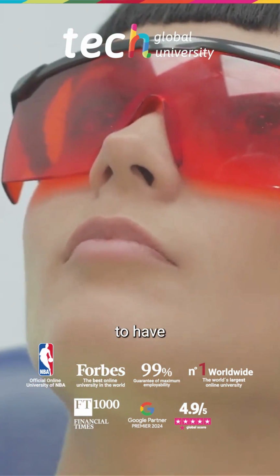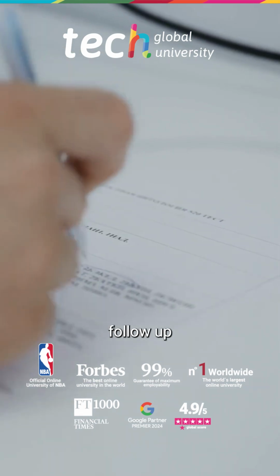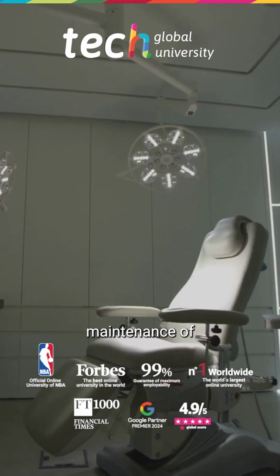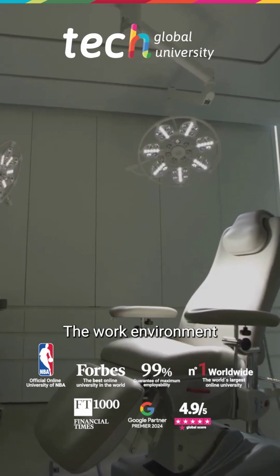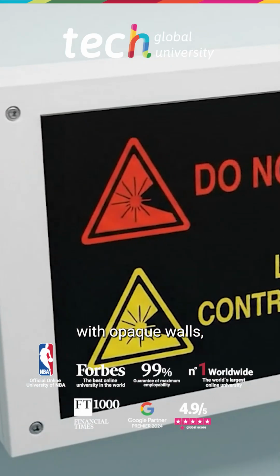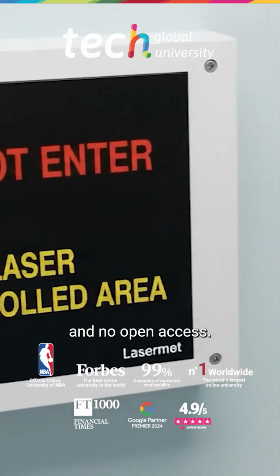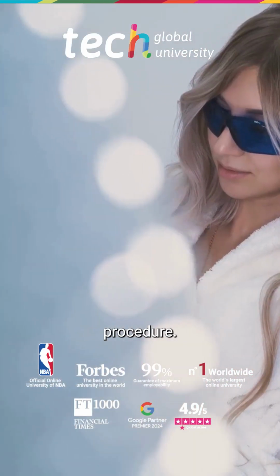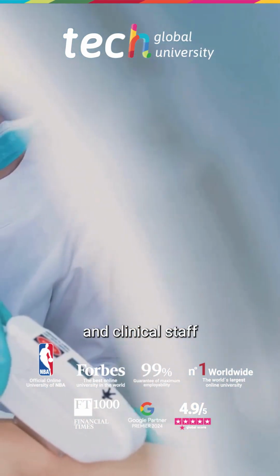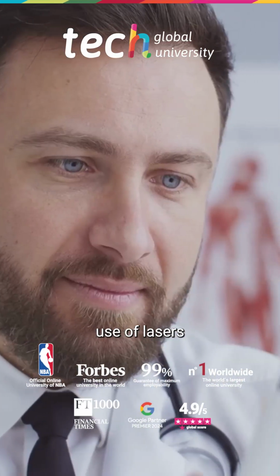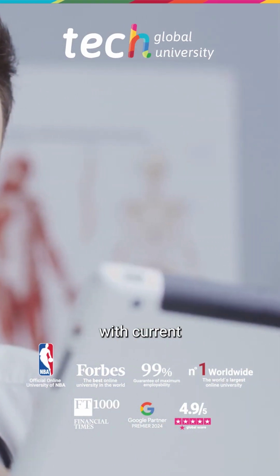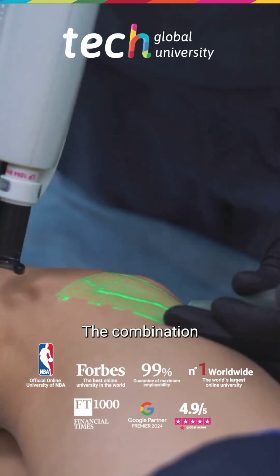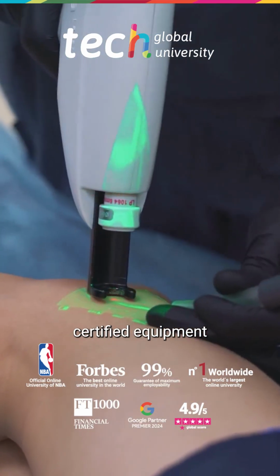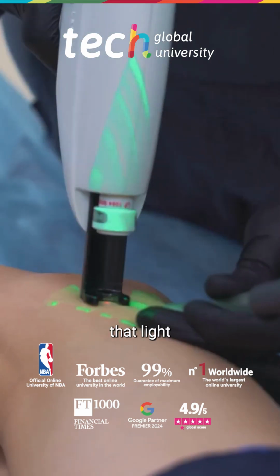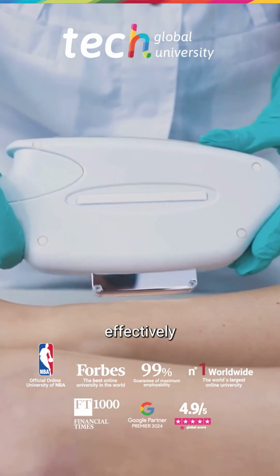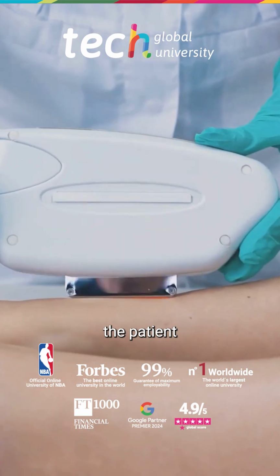It is also recommended to have standardized work protocols, follow-up sheets, and documented preventive maintenance of the equipment. The work environment must be controlled, with opaque walls, visible laser signage, and no open access during the procedure. Training of both technical and clinical staff in the safe use of lasers is essential, as is compliance with current regulations. The combination of correct technique, certified equipment, and protective barriers ensures that light-based treatments are performed effectively and without risk to either the patient or the professional.